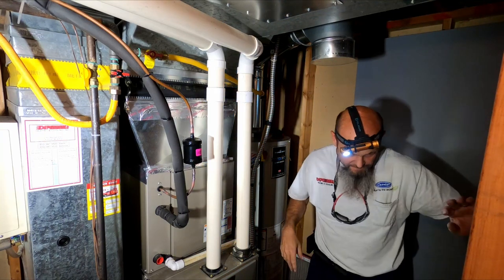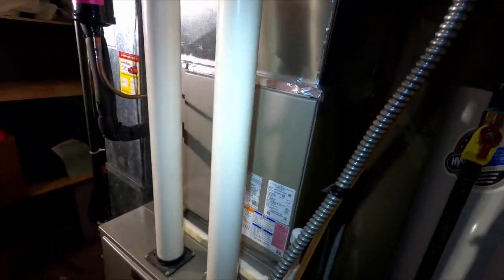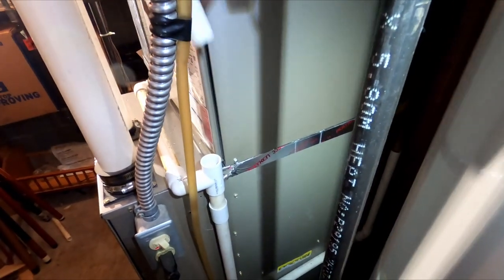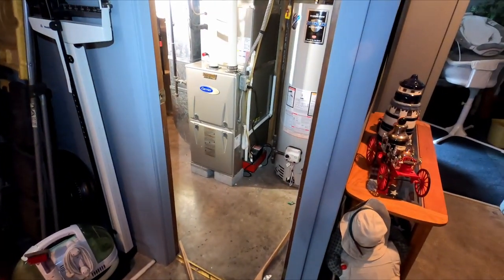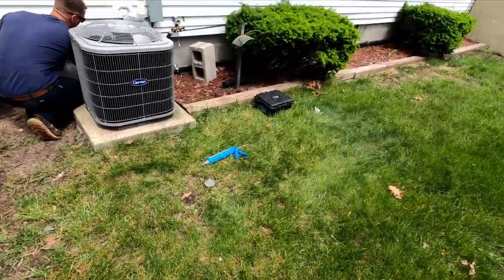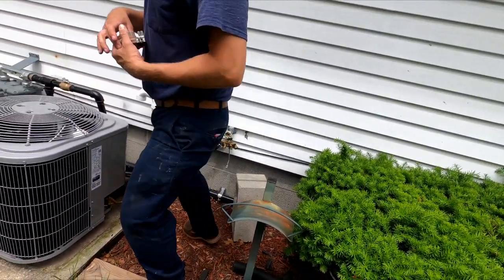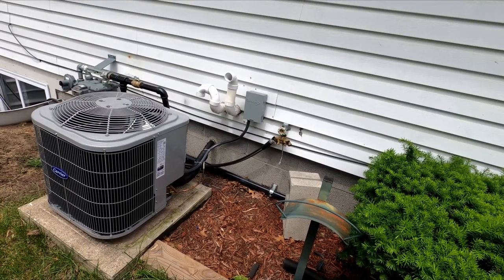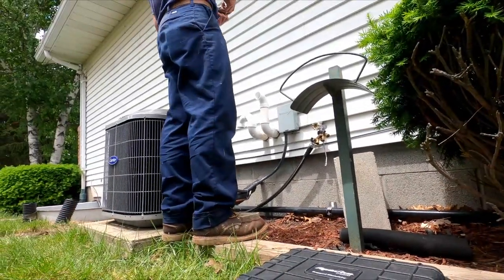And we are ready to start. I gotta get a filter. Clean out. It is what it is. Alright, let me go get a filter, and we'll start this puppy up. Get some pressures. Yeah, I just opened this up. Now about to throw the fuses in. Do we got the power on the other one? I gotta go put that disconnect in there. All right, let me go put that disconnect in and we'll hook the gauges up and get it running. She's already calling. Oh, you know, it probably would help to turn the furnace on downstairs, huh?